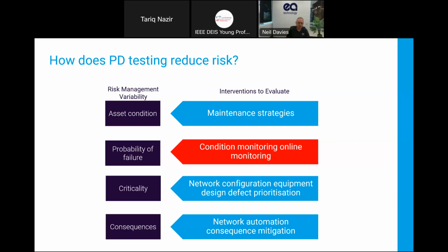Other ways that we can reduce the risk on the network, of course, is to design it right, and network automation, so that we can mitigate against the consequences of any particular failure. But condition monitoring is reducing the probability of failure and then allowing you to intervene in that maintenance strategy.